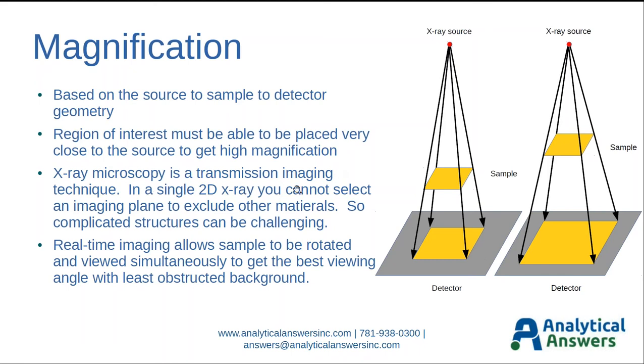One thing to keep in mind: X-ray microscopy is a transmission imaging technique. It's not like you have a depth of field where you can select a particular imaging plane. You basically see everything that's between the source and the detector. If you have very complicated structures, it can be very challenging to see the layer of interest. That's one of the advantages of real-time imaging that you can really select the proper viewing angle for every sample. Sometimes fractions of a degree are required to really go from an image that shows you what you need to see to not being able to see anything at all.